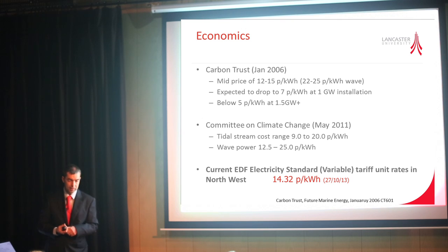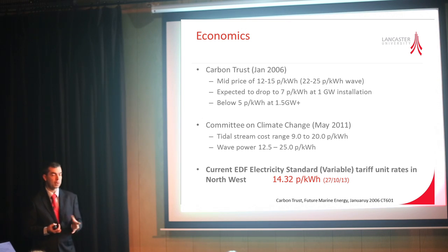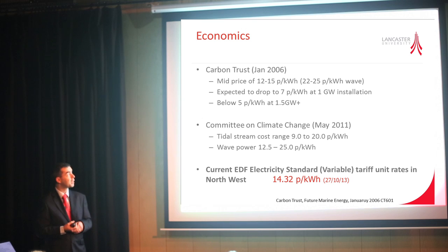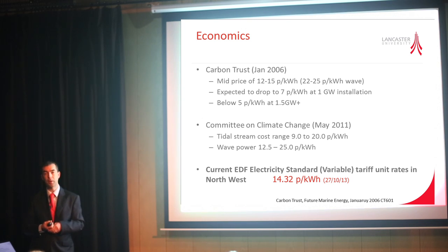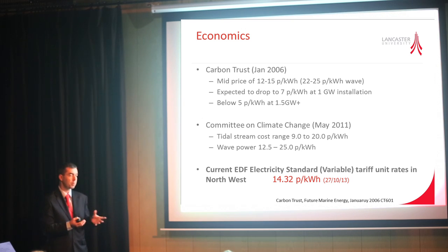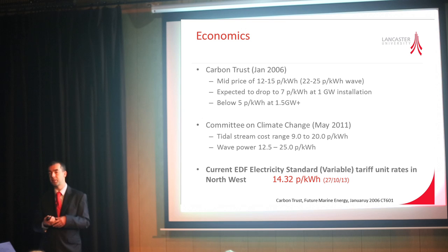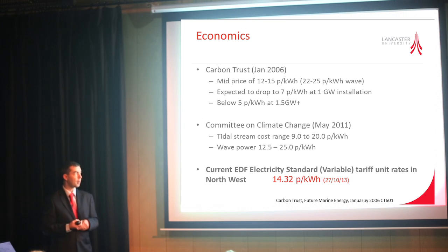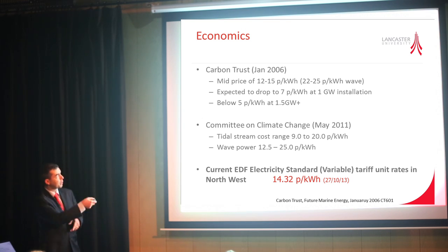In terms of the economics, it's no good just having lots of power if we can't extract it economically. So looking at some of this, typical cost estimates back in 2006 put tidal energy in the 12 to 15 pence per kilowatt hour bracket. As we install more, we get savings in terms of mass manufacture, improvements in installation procedures, and reduced maintenance requirements. That price is predicted to fall to potentially below 5 pence per kilowatt hour at the 1.5 gigawatt installation point. Similarly, the more recent report in 2011 was suggesting somewhere between 9 to 20 pence.